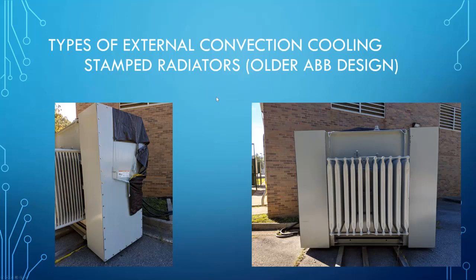This is Michael, I think one good thing to add on this particular type of fin is this is the most common way for pad mount. So if you're specifying a pad mount, typically it's going to come with this type of fin by default, just the way they're inherently designed. If you go to a unit substation, Michael's got some slides that are preceding that show more options for unit substation, but 99% of the time all pad mounts are going to have that fin type design for the radiators. Adam is absolutely correct, although there are occasions where larger pad mounted units will require radiators. The kVA is dependent on the manufacturer, but ultimately you're going to have to go to radiators at some point.